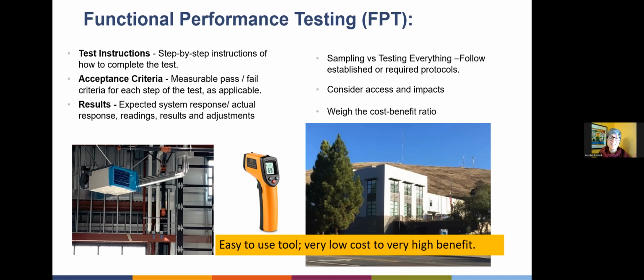And then a couple of these pictures, and this tool is from the commissioning agent we work with, has a story where, very easy to use, a temperature gun where you can use that to measure the temperature of outcoming air, for example supply air, and it appeared that all the equipment was working. But through this process of sampling and just making a few measurements here and there, it has a very easy to use tool. It's very low cost, has very high benefit.